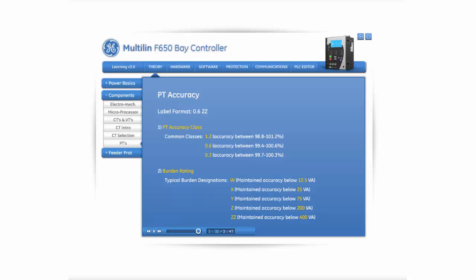In this example, the PT rated 0.6 double Z would have an accuracy between 99.4 to 100.6% as long as the burden of the PT remains under 400 volt amperes.